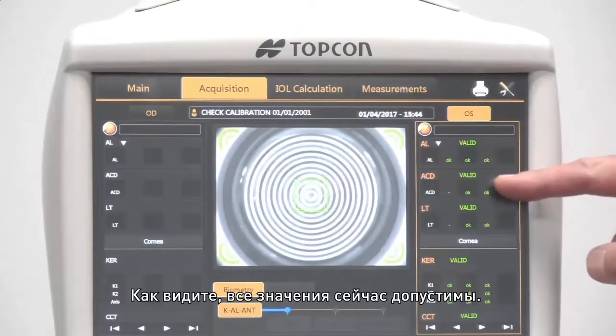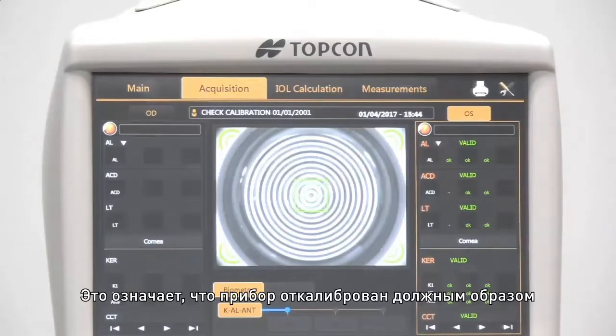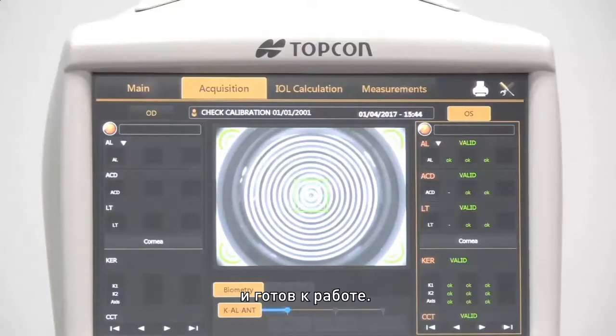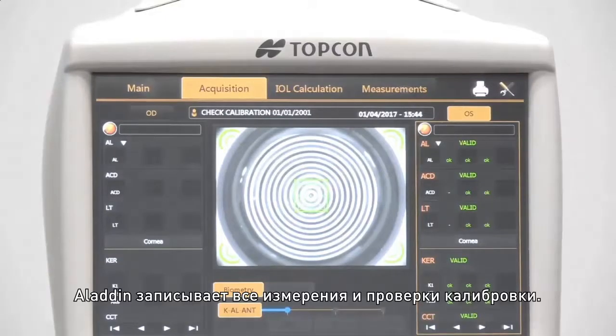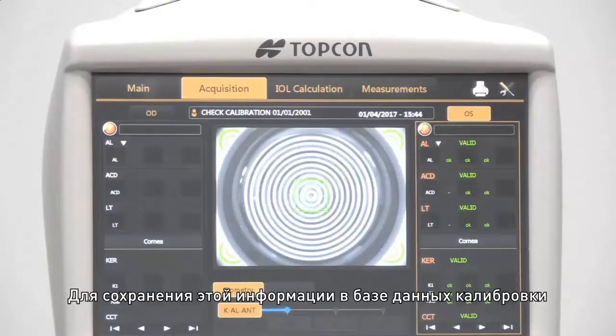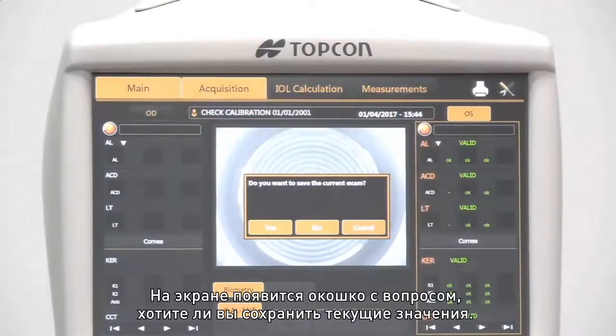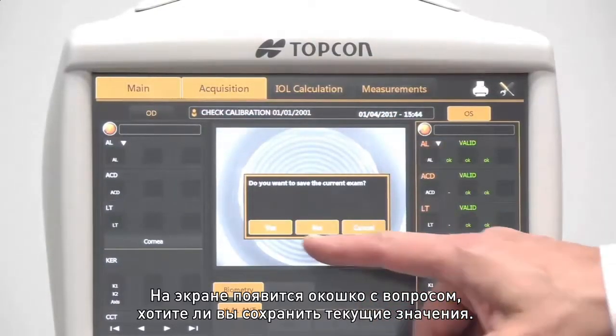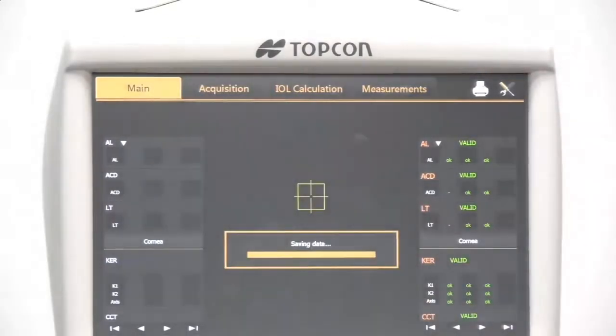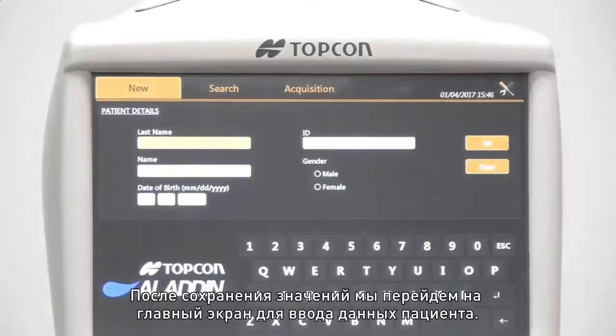As you see, all the measurements now are valid, therefore the instrument is properly calibrated and it can take measurements from patients. The Aladdin keeps track of all the measurements and the calibration checks. In order to save this information in the calibration check database, we press main, and the instrument is going to ask us if we want to save the values. We say yes. And now we're in the main screen ready to enter a patient.